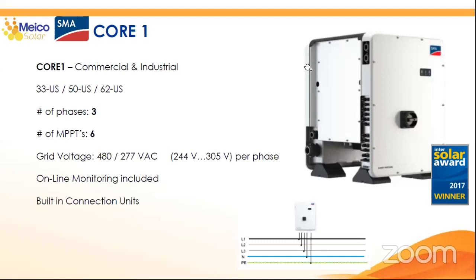I'm going to explain why, but normally roof projects. There are three different powers: 33 kilowatt, 50 kilowatt, and 62 kilowatt. It's the same size, the same inverter; the only difference is the power. The exit of the inverter is three phases, as you can see here. Each phase is from 244 volts to 305 volts, so grid voltage of 480, between 440 to 480 volts.